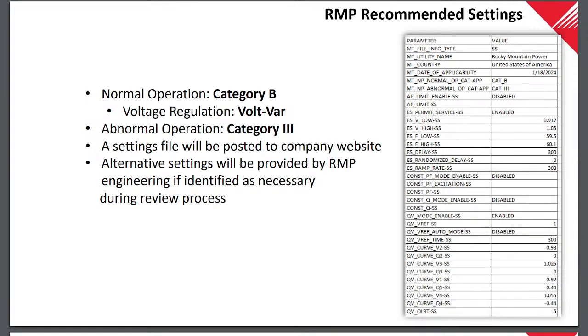You can see the power factor mode is disabled, and the QV mode is enabled, so that's where our volt-var is set. Then we have our curves down there, the V1s and Q1s, and 2s and 3s. So that's kind of what we're proposing to do with that.